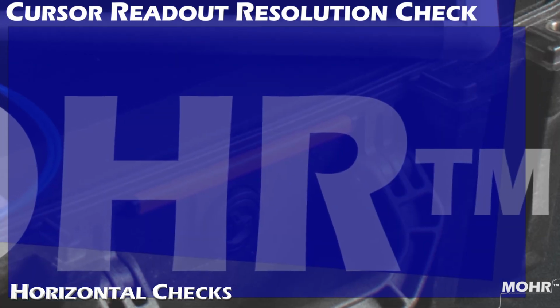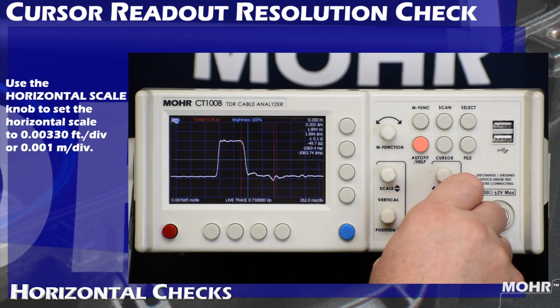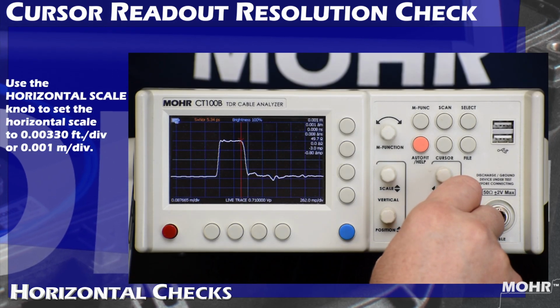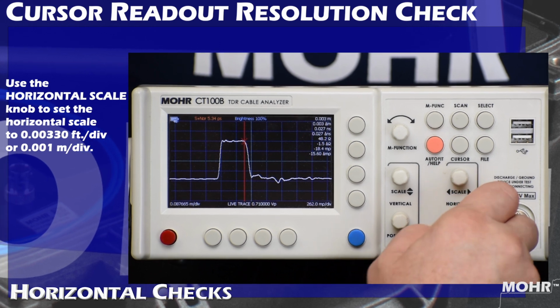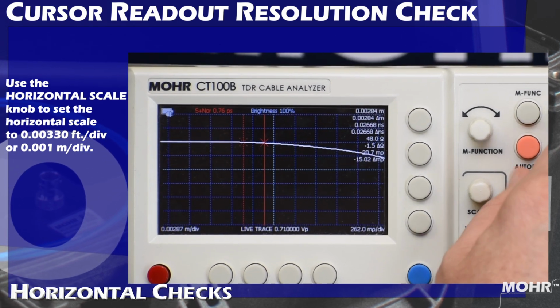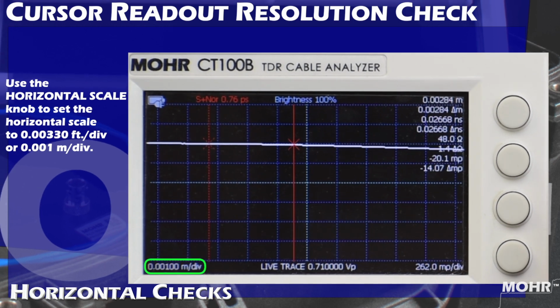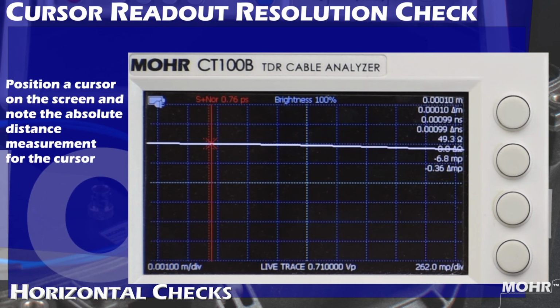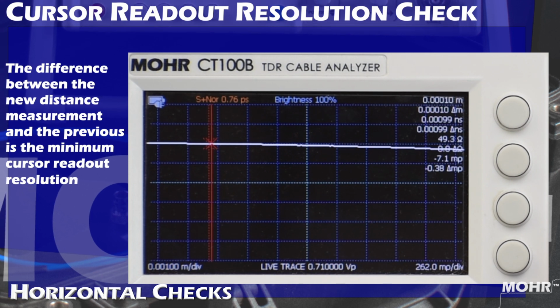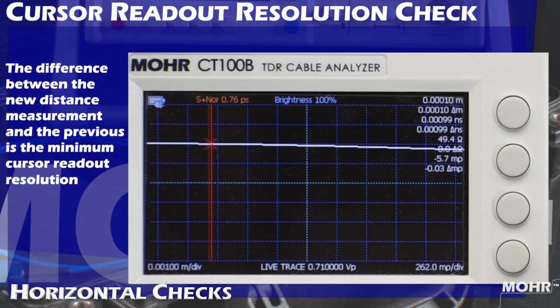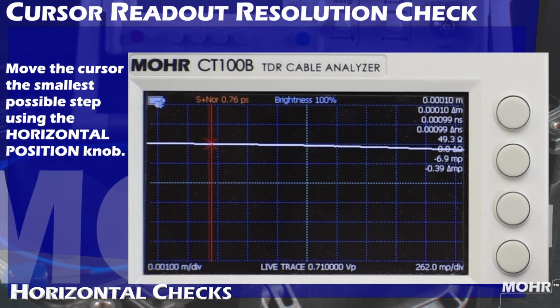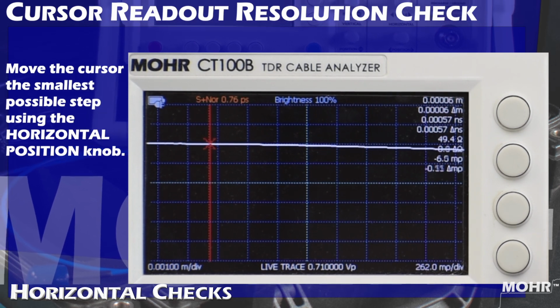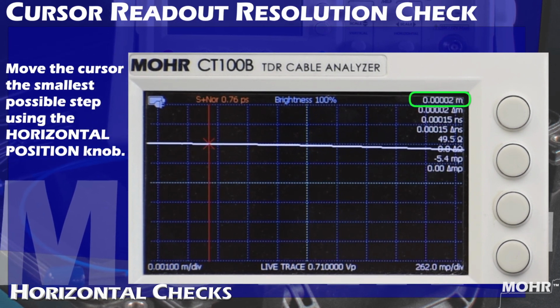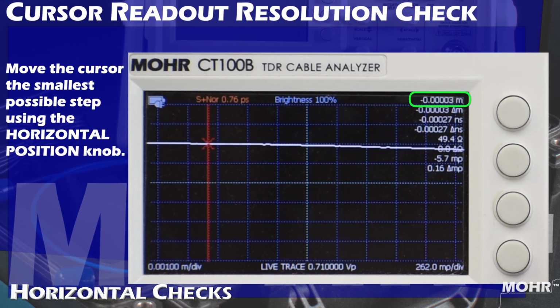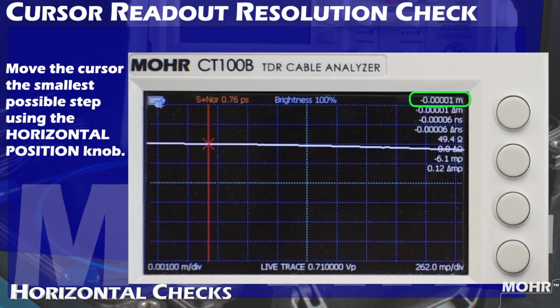As for the horizontal position check, this test is passed implicitly when the cursor readout range and horizontal range checks are passed. For the cursor readout resolution check, I'm going to use the horizontal scale knob to set the horizontal scale to 0.00330 feet or 0.001 meters per division. Position a cursor on the screen and note the absolute distance measurement for the cursor. Move the cursor the smallest possible step using the horizontal position knob. The difference between the new measurement and the previous measurement is the minimum cursor readout resolution.